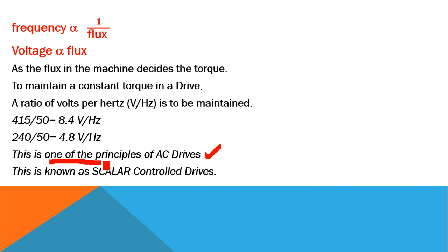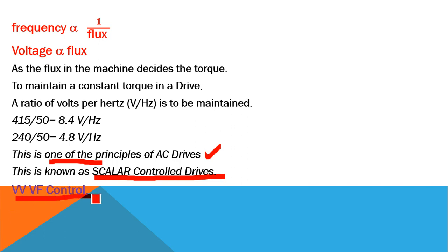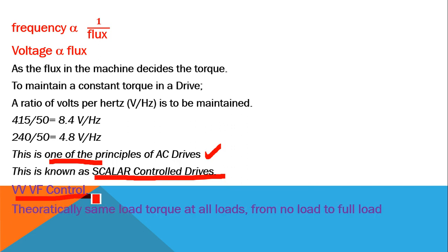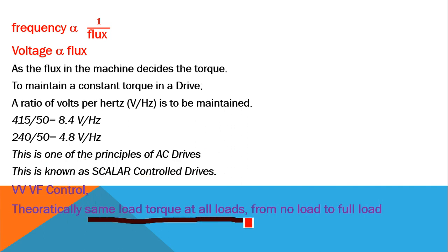This type of drive control is known as scalar controlled drives, or otherwise known as variable voltage variable frequency (VVVF) control. Theoretically, with this method of control, we get almost the same torque at all conditions - from no load to full load, the motor torque will not vary. In a conventional method, if you are starting the motor, the torque may be different. But the advantage of VVVF control or VFD in the scalar method is that it will have constant torque from no load to full load.